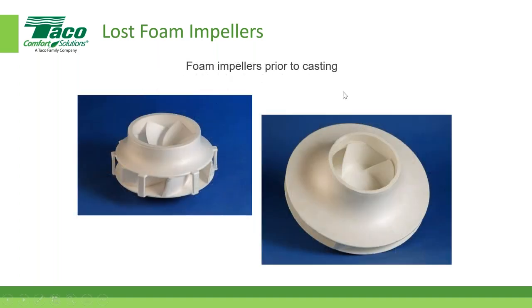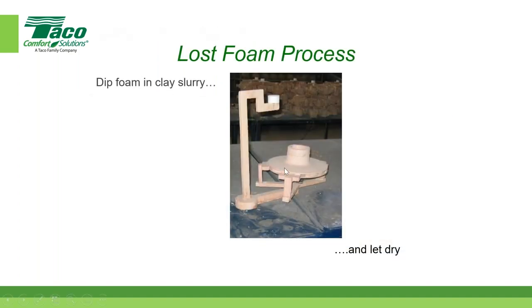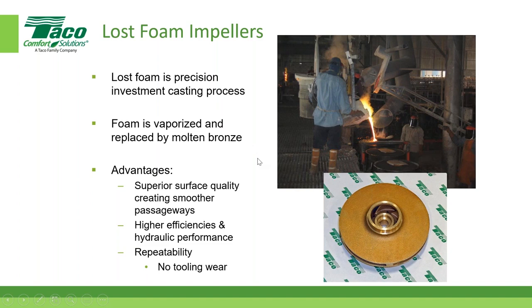Here's a picture of the foam impeller prior to casting. It's just a piece of foam that replicates the impeller 100%. Then you dip the foam in a clay slurry and let it dry. So this is an investment casting process. Now the foam is vaporized and replaced by molten bronze. You can see the advantages there: superior surface quality, creating smoother passageways, higher efficiencies in hydraulic performance, and really the most important part is repeatability, no tooling wear.